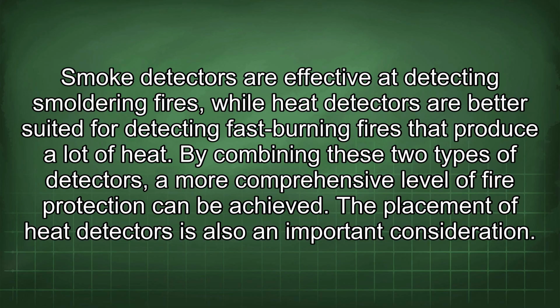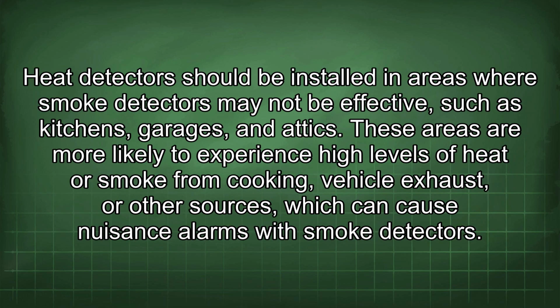Smoke detectors are effective at detecting smoldering fires, while heat detectors are better suited for detecting fast-burning fires that produce a lot of heat. By combining these two types of detectors, a more comprehensive level of fire protection can be achieved. The placement of heat detectors is also an important consideration. Heat detectors should be installed in areas where smoke detectors may not be effective, such as kitchens, garages, and attics.